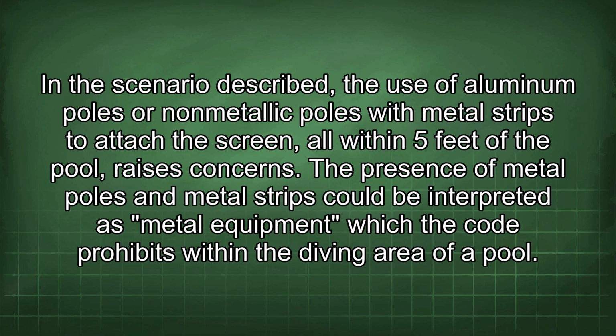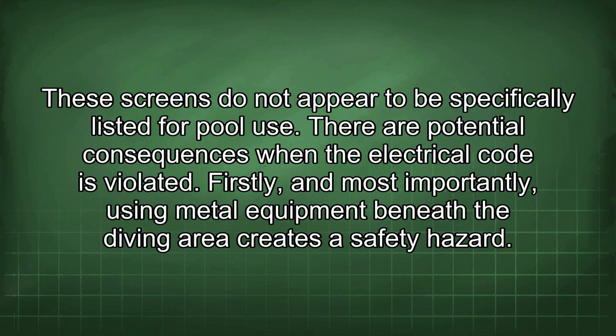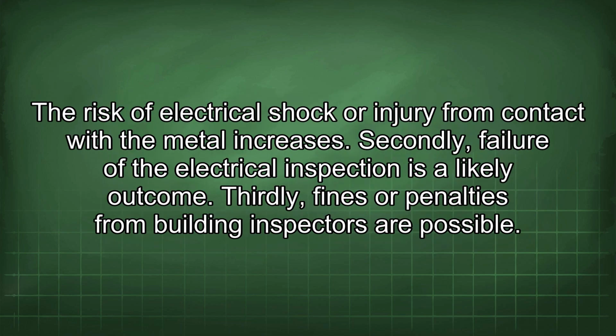The presence of metal poles and metal strips could be interpreted as metal equipment which the code prohibits within the diving area of a pool. These screens do not appear to be specifically listed for pool use. There are potential consequences when the electrical code is violated. Firstly, and most importantly, using metal equipment beneath the diving area creates a safety hazard. The risk of electrical shock or injury from contact with the metal increases.